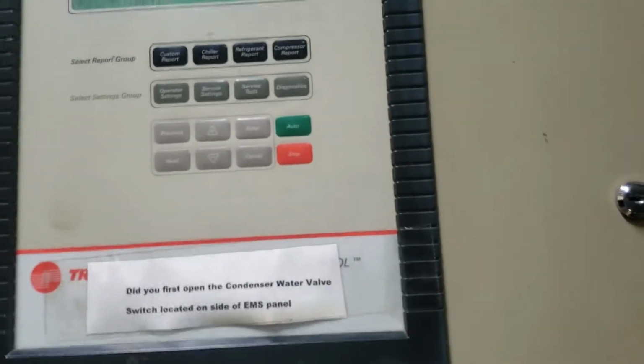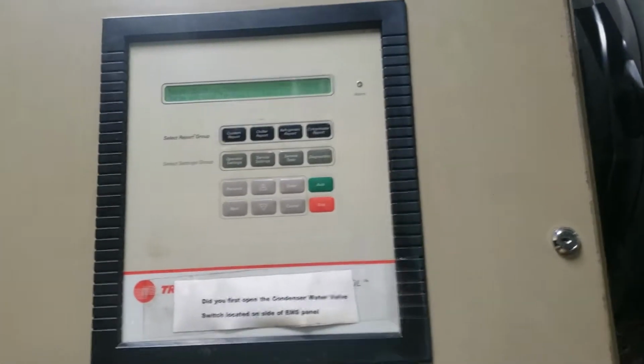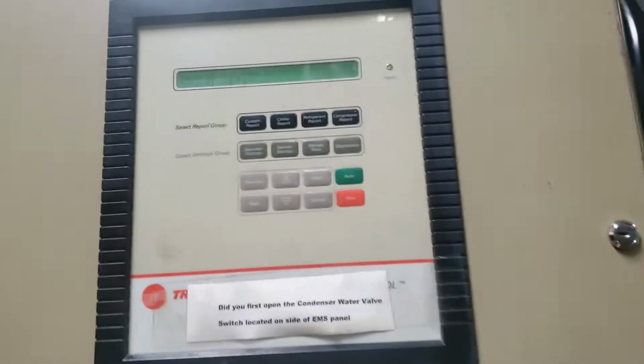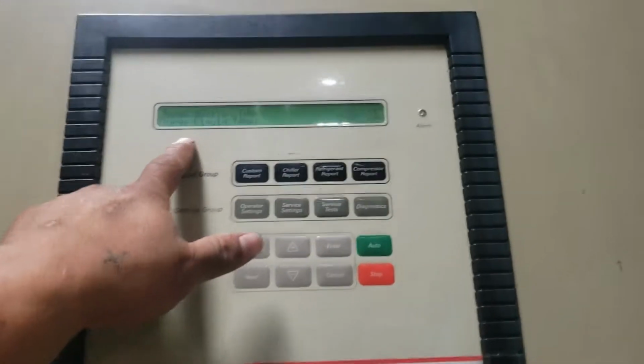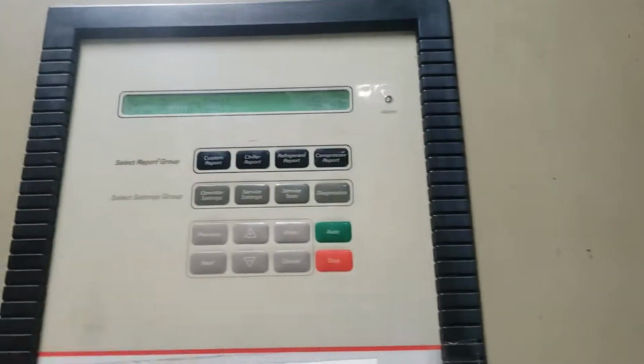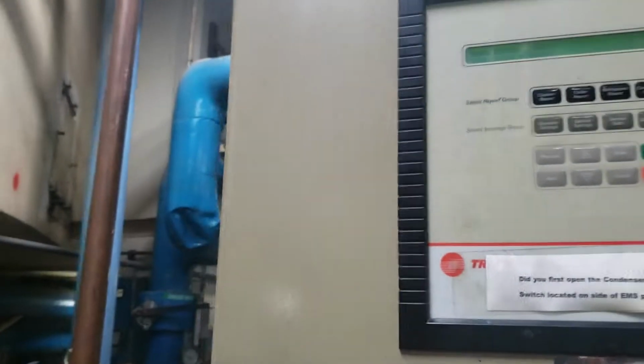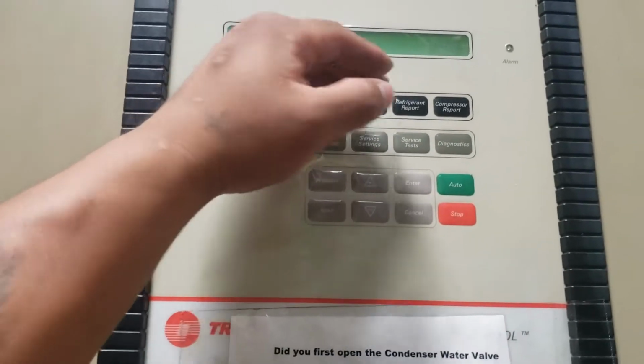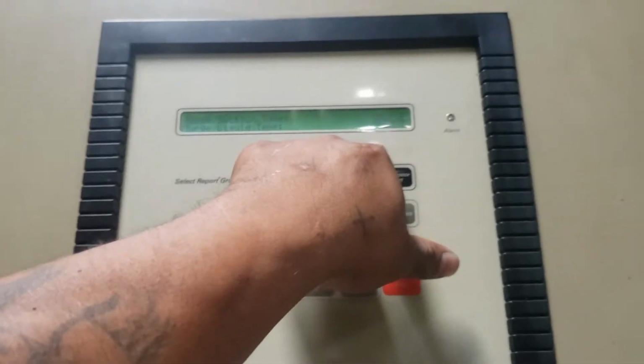Okay guys, I'm over here troubleshooting this Purge unit. It seems like it's just running constantly, pumping out constantly, but that's why I'm here checking it. Right now my Purge suction temp is 58, so that's telling me that the evaporator, which is that Purge tank right there, has nothing but vapor refrigerant coming from the condenser of the chiller. So that's what keeps up the suction temp inside the evaporator of that Purge unit.